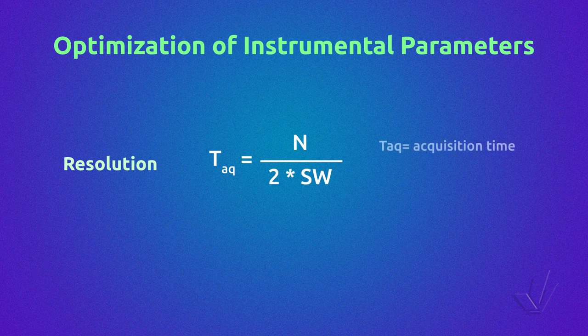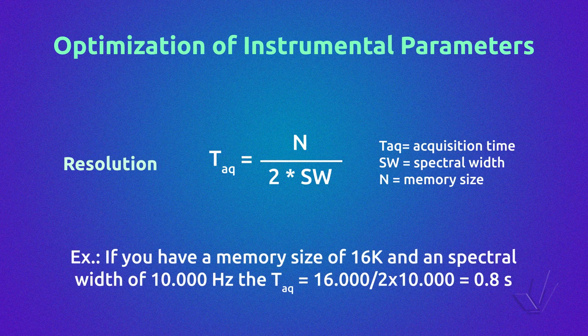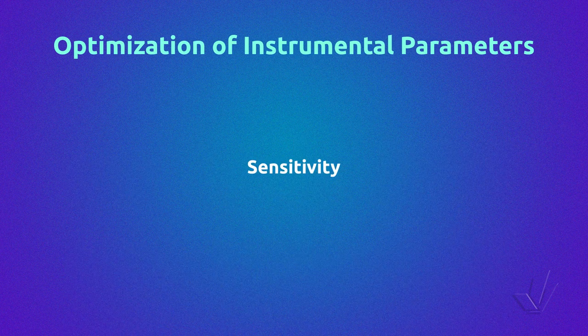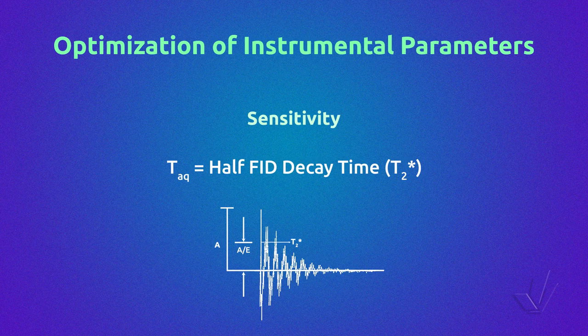Optimization of instrumental parameters should lead to a spectrum with good resolution and sensitivity. The following equation relates acquisition time with spectral width and memory size. For example, with a memory size of 16K and a spectral width of 10,000 Hz, the acquisition time should be 0.8 seconds. To have good sensitivity — a high signal-to-noise ratio — the acquisition time should equal the half-FID decay time. When both sensitivity and resolution are important, a compromise must be reached.